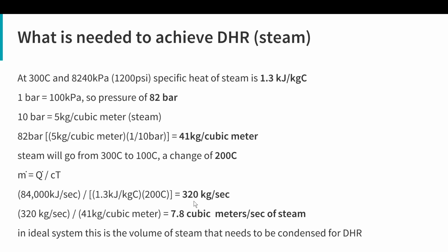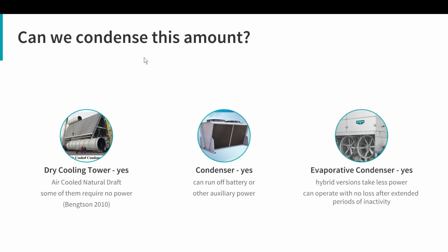And what's the volume of that steam? It's going to be 7.8 cubic meters per second. So we need 6, maybe 10 fire pumps that pump 750 gallons a minute. And then we're going to need to condense 7.8 cubic meters per second of this steam. In an ideal system, this is the volume of steam that needs to be condensed. So can we condense this amount? Looked at a bunch of products and looks like yeah.